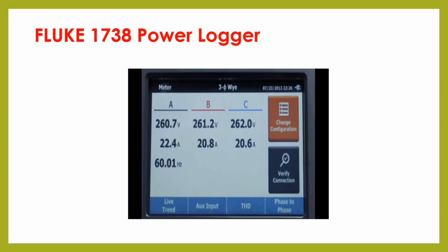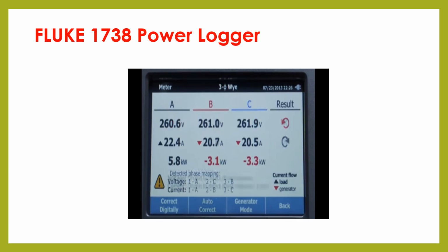Once the power is back online, press the Verify Connection button. The instrument will let you know if things are correct or show where you may have made a mistake. If a mistake has been made, you can fix it on the instrument without having to disconnect anything using the Autocorrect button.